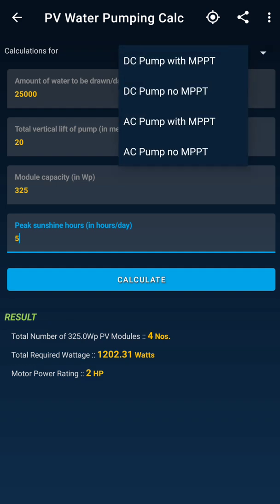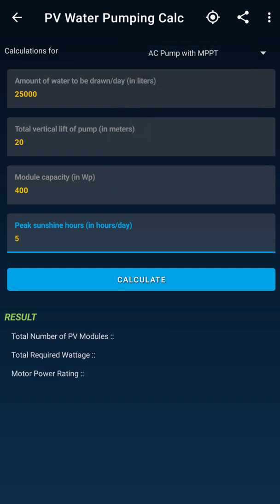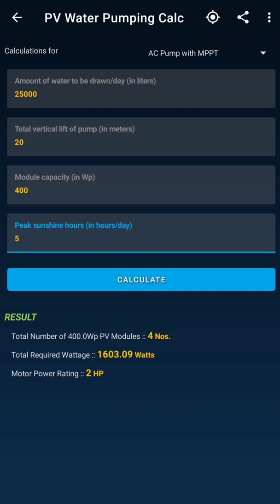Just in case you use an AC pump with an MPPT, I select AC pump with MPPT — the configuration remains the same — and hit Calculate. The total required wattage has increased. In a pure DC system there are fewer losses, but if you are running a DC-to-AC device, the inverter conversion introduces additional losses, which increases the wattage requirement.